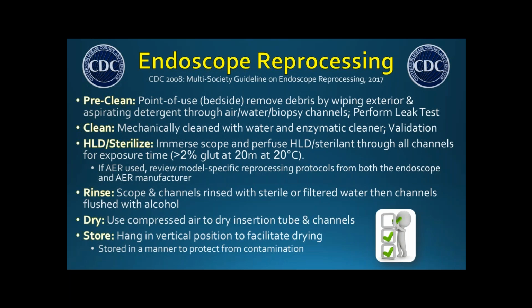There's things like channel check, where you can run sterile water through the lumen of the scope after you perform the first cleaning step to see if there's any carbohydrate, blood, or protein left in the scope. You can also use visual inspection. They have the inspectoscope, where you can do visual inspection of your scope to see if you have anything missing or any damage to your scope. And then after you have that proper cleaning process, then doing your high-level disinfection or your sterilization.